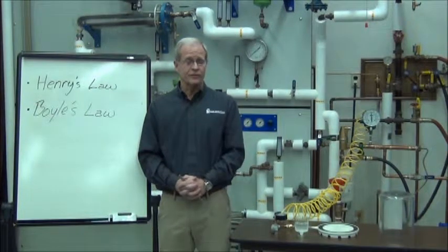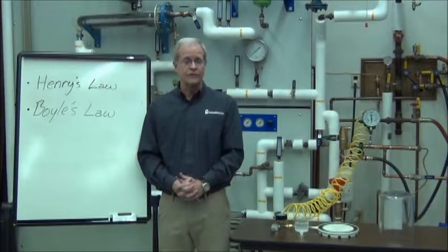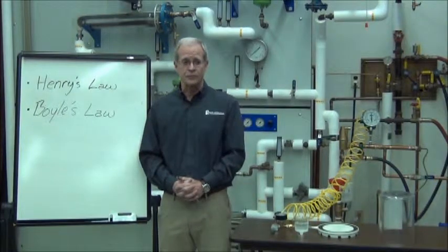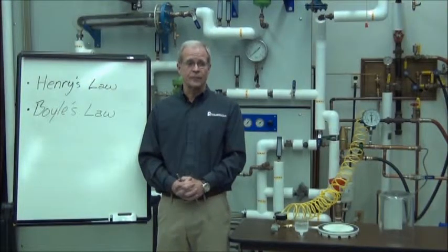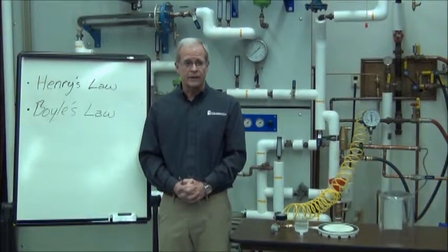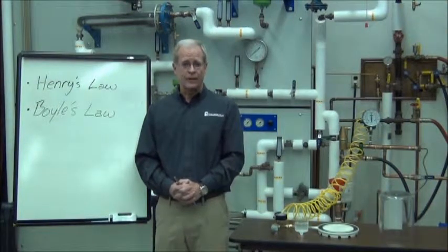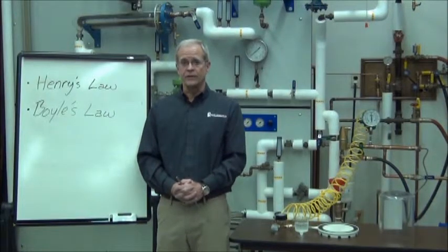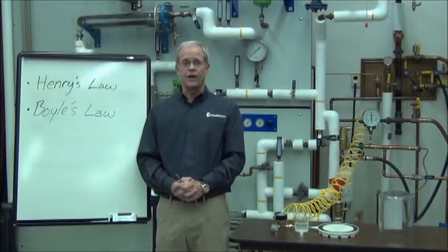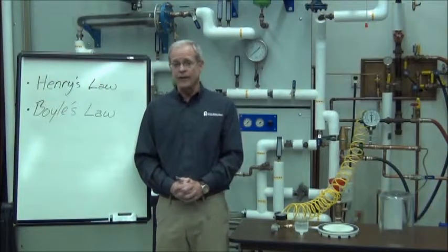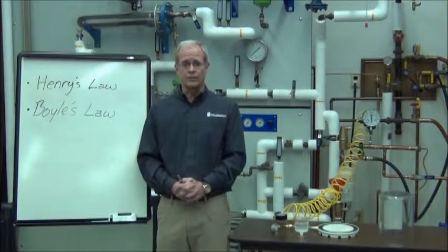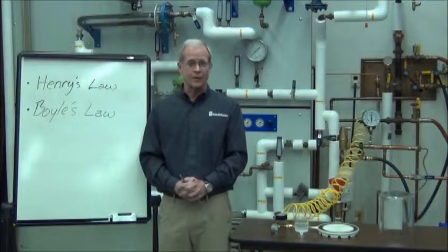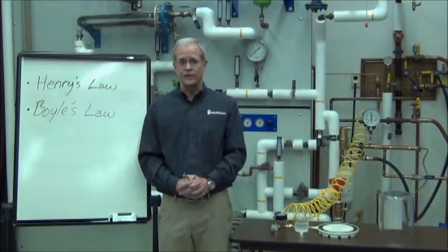And as I said, the application for this is in cooling towers where we have a lot of dissolved air that we can't see and entrained air, which may be in microscopic bubbles to larger bubbles. But when that fluid enters the suction side of a pump, there's a sharp pressure reduction, and we're going to do a little experiment to show you what can happen when we have a fluid with some dissolved gas in it. The fluid we have is some kind of flat carbonated water. This is about a year-old carbonated water, and we're going to subject that to low pressure and see what happens to it.